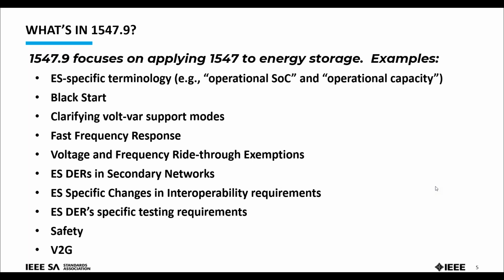I also want to briefly point out the last bullet: V2G, vehicle to grid. That's becoming a fairly hot topic in the standards community. Part of the issue is that for certain V2G configurations, 1547 has commissioning tests—when a distributed energy resource, or DER, is built, someone from the utility comes out, goes through a checklist, confirms everything's up and running, and away you go. But if I have a V2G-capable charging system from one manufacturer and I pull up with a vehicle from any other manufacturer, that system could be changing all the time.